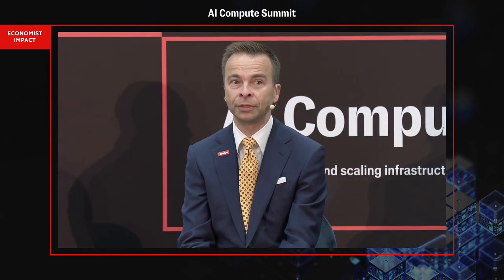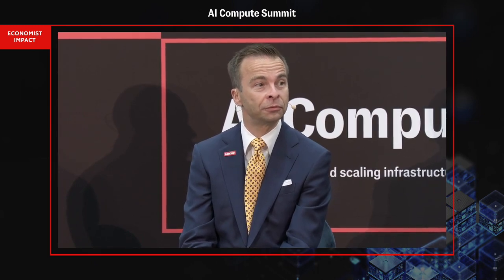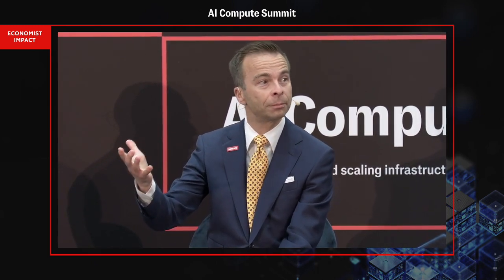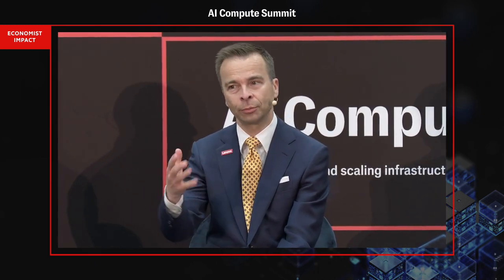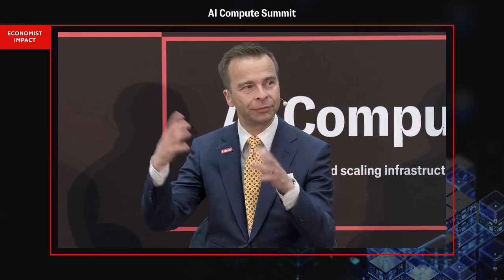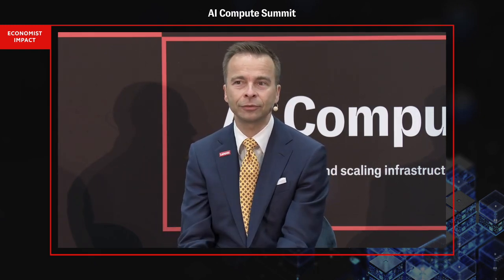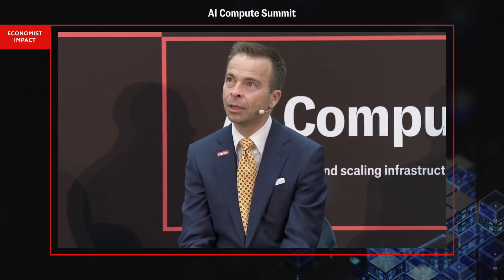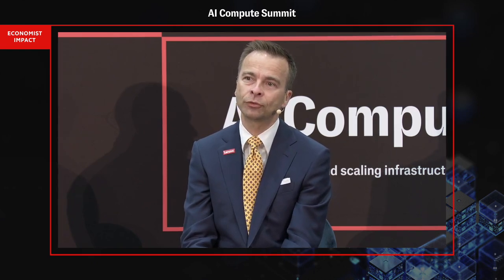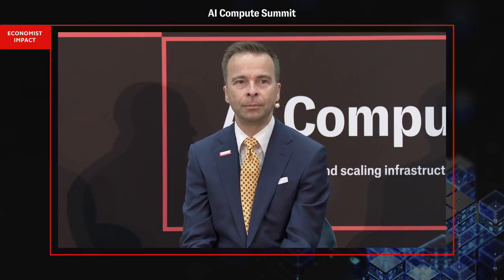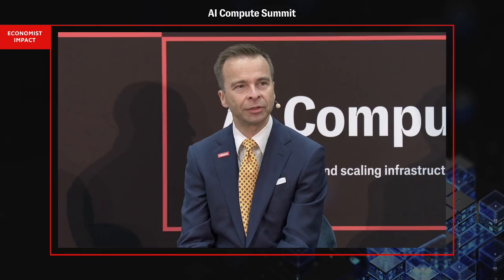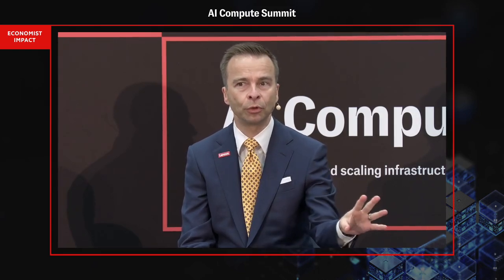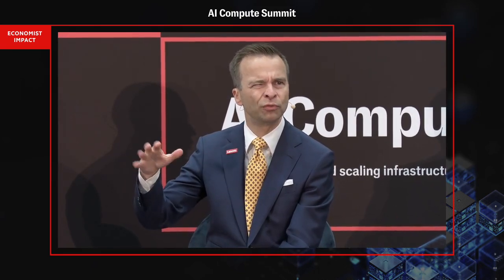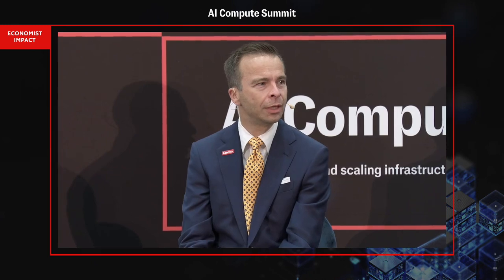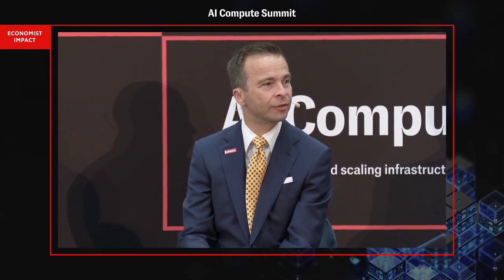That's typically reflected in the PUE, and there's a lot of debate about how you measure that correctly—I won't get into that. But the difference between a mostly water-cooled versus a mostly air-cooled data center, opinions vary, is probably somewhere between 1.1 or better for water-cooled, versus 1.4 or worse for air-cooled. So you have a 30% plus difference there again.